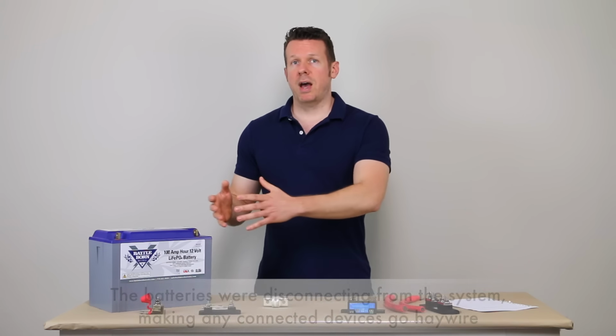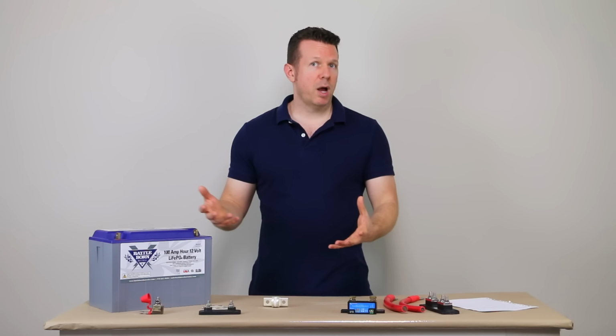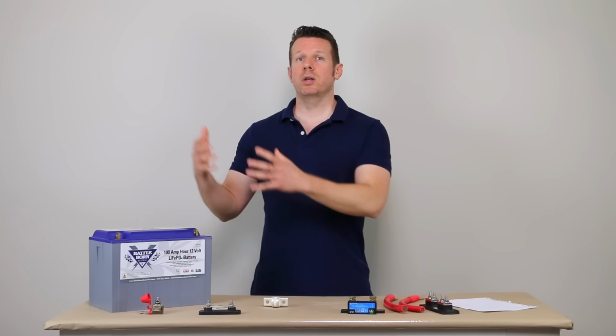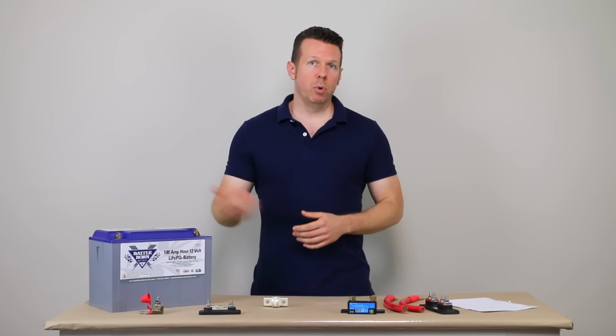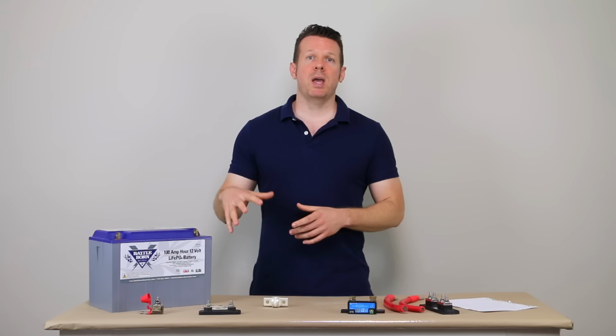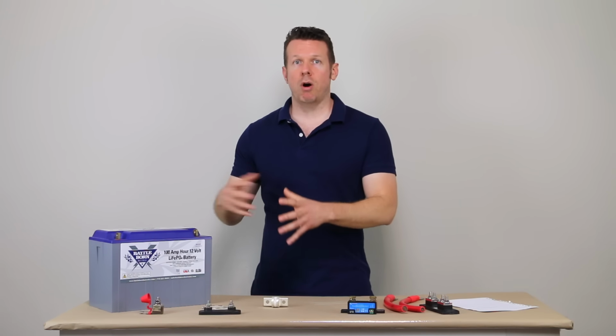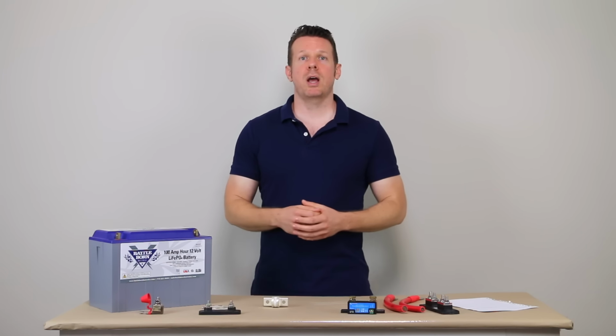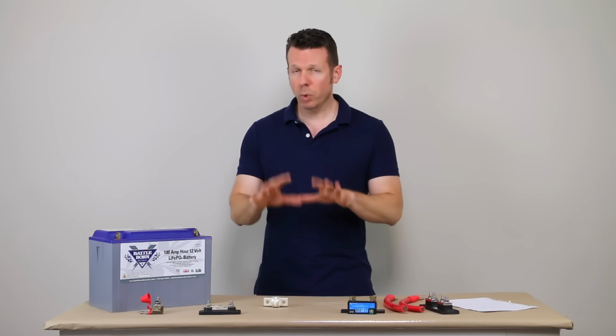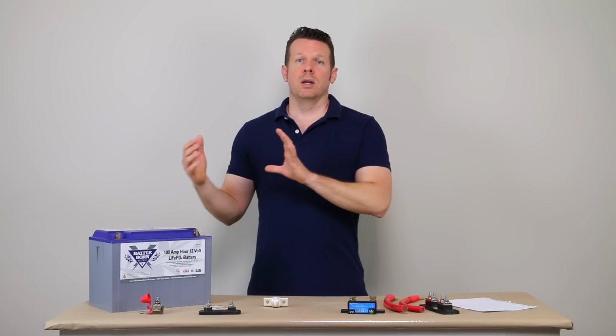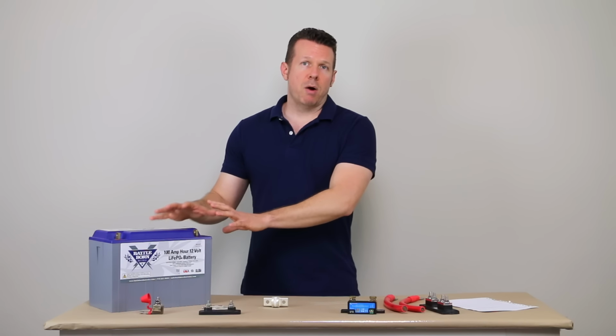He thought something was wrong with the inverter charger and wasn't sure why it was shutting down. On the flip side, when he would run most appliances, everything was fine, but when he would run the stove, it pulled more than 100 amps out of that battery bank, and the stove would shut off - a mysterious shutdown again.